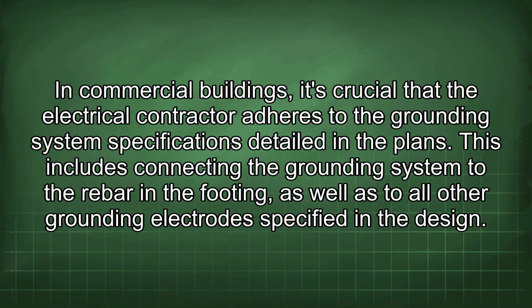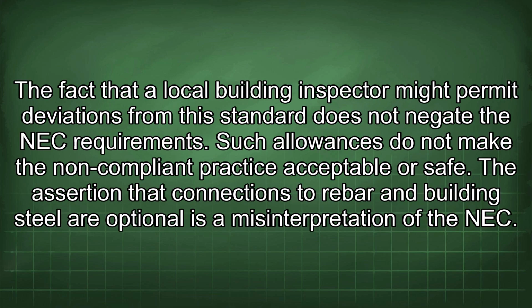In commercial buildings, it's crucial that the electrical contractor adheres to the grounding system specifications detailed in the plans. This includes connecting the grounding system to the rebar in the footing, as well as to all other grounding electrodes specified in the design. The fact that a local building inspector might permit deviations from this standard does not negate the NEC requirements. Such allowances do not make the non-compliant practice acceptable or safe. The assertion that connections to rebar and building steel are optional is a misinterpretation of the NEC.